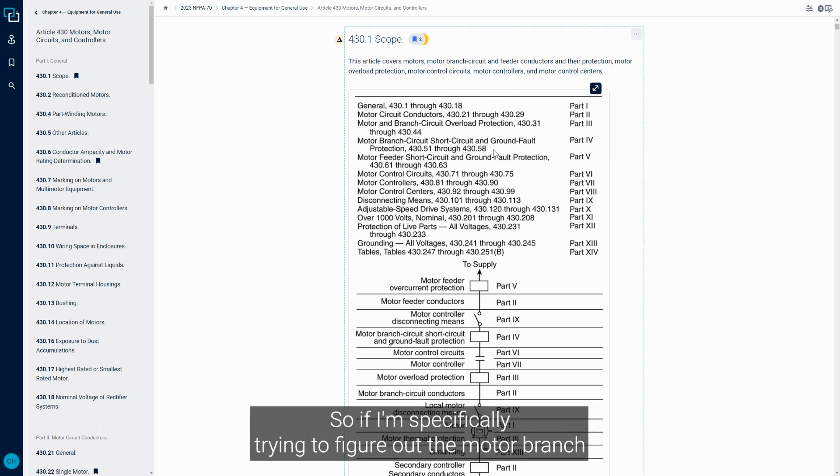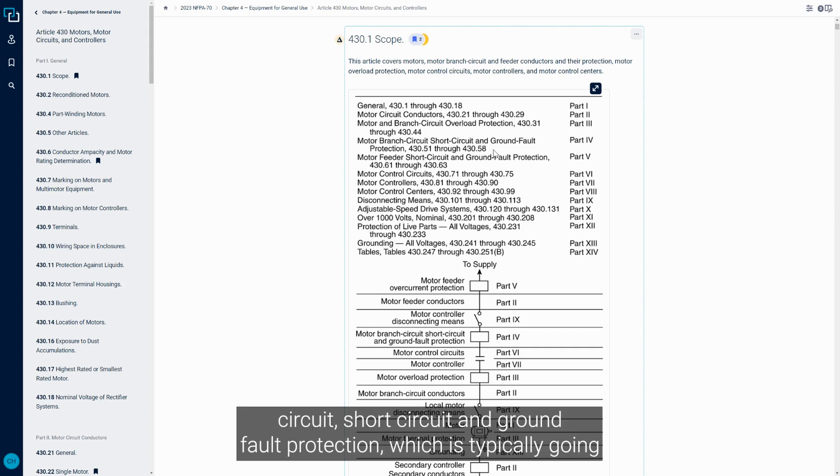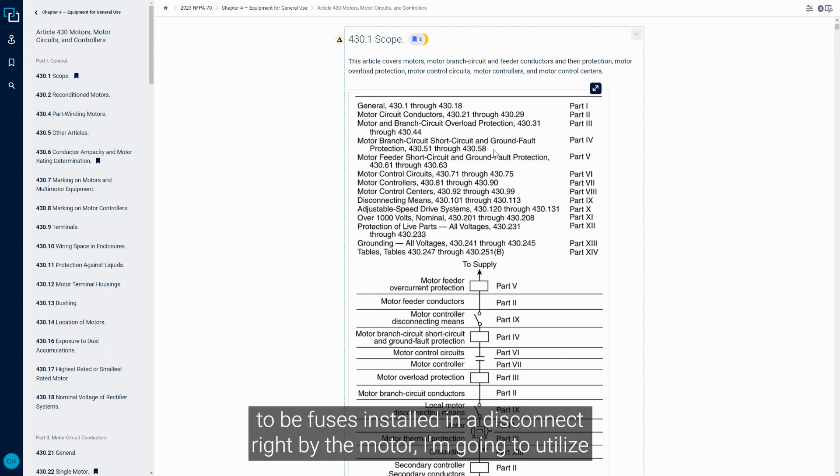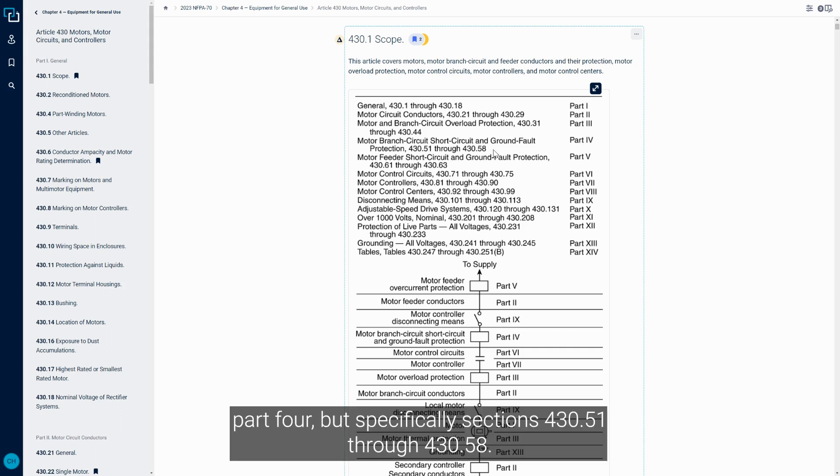If I'm specifically trying to figure out the motor branch circuit short circuit and ground fault protection, which is typically going to be fuses installed in a disconnect right by the motor, I'm going to utilize Part 4, specifically sections 430.51 through 430.58.